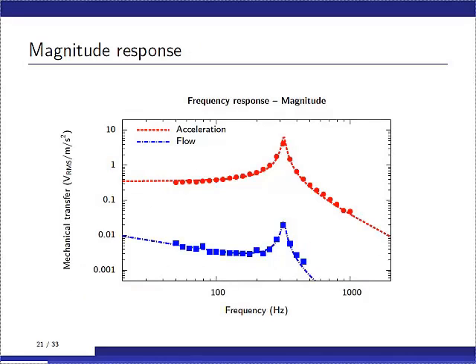Horizontally the frequency, and vertically the mechanical transfer, which is the output voltage in RMS per meter per second squared. And the idea about flow is that you have flow velocity, and if you are in the frequency domain, which we are over here, then we can multiply, or we can use the frequency properties to convert it to an acceleration.